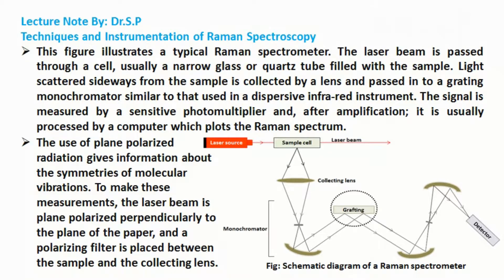The laser beam is passed through a cell, usually a narrow glass or quartz tube filled with the sample. Light scattered sideways from the sample is collected by a lens and passed into a grating monochromator, similar to that used in a dispersive infrared instrument. The signal is measured by a sensitive photomultiplier and, after amplification, it is usually processed by a computer which plots the Raman spectrum.